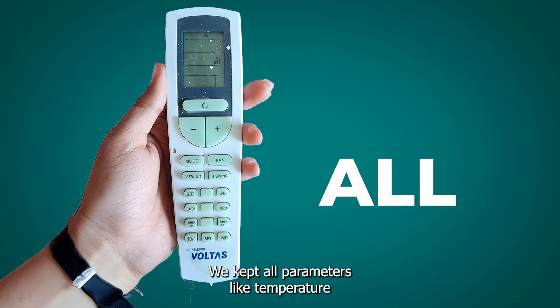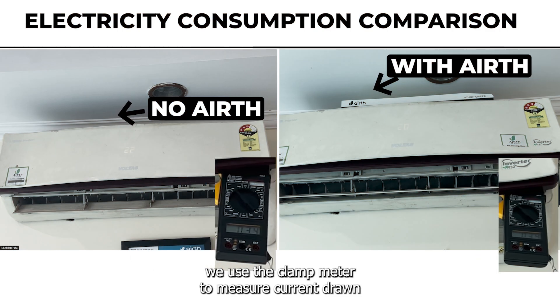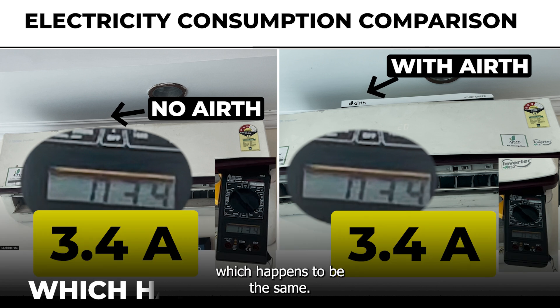We kept all parameters like temperature, mode, and fan speed constant. Then we used the clamp meter to measure current drawn in cool mode without Airth installed. The current drawn was around 3.4 amps. And with Airth installed, it was again around 3.4 amps — which happens to be the same.